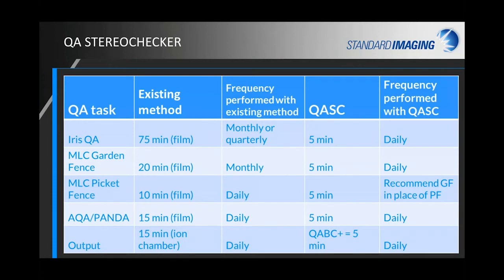People often ask how we decide what products to bring to market. We worked with a clinical physicist knowing that the existing methods for QA on the CyberKnife system — especially with the newer S7 or M6 that added MLCs — are still stuck with film, which is an inefficient way of getting QA done and generally requires a physicist. Also, CyberKnife is a stereotactic machine, so you really want to think about whether you're satisfied doing certain QA only quarterly, when a fast, efficient method could allow you to do it daily for those high dose rate hypofractionated treatments.